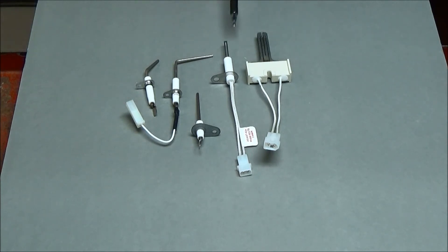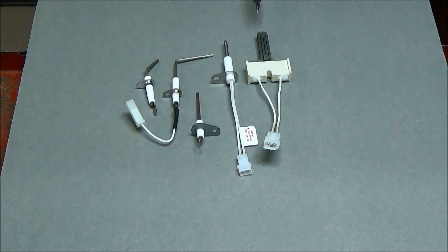Once that time cycle is out, the hot surface igniter will energize and begin to glow orange. We have two different types of igniters here for different applications. Once this igniter reaches a certain temperature, the main gas valve will open.